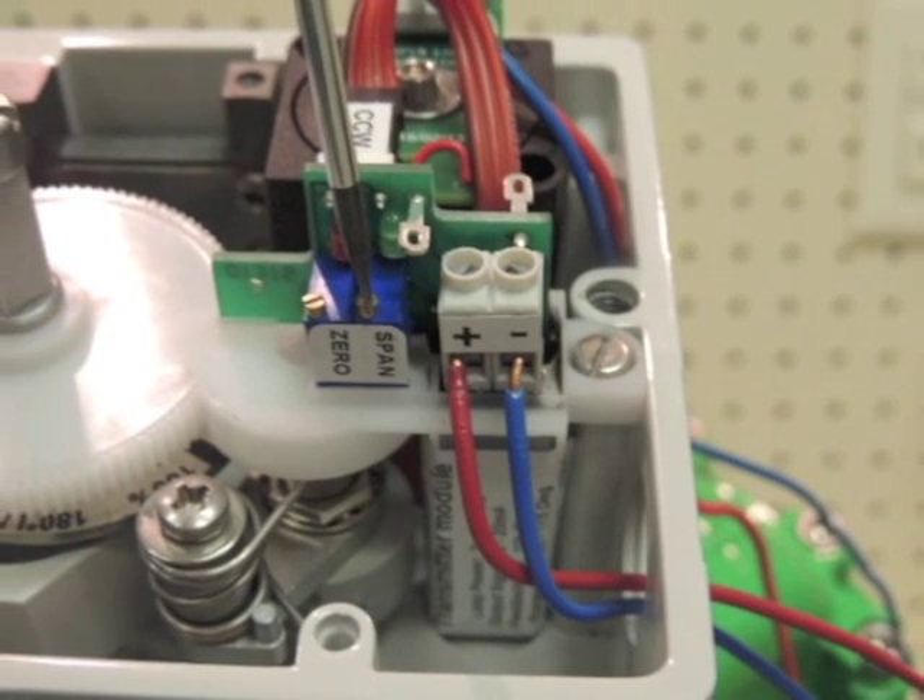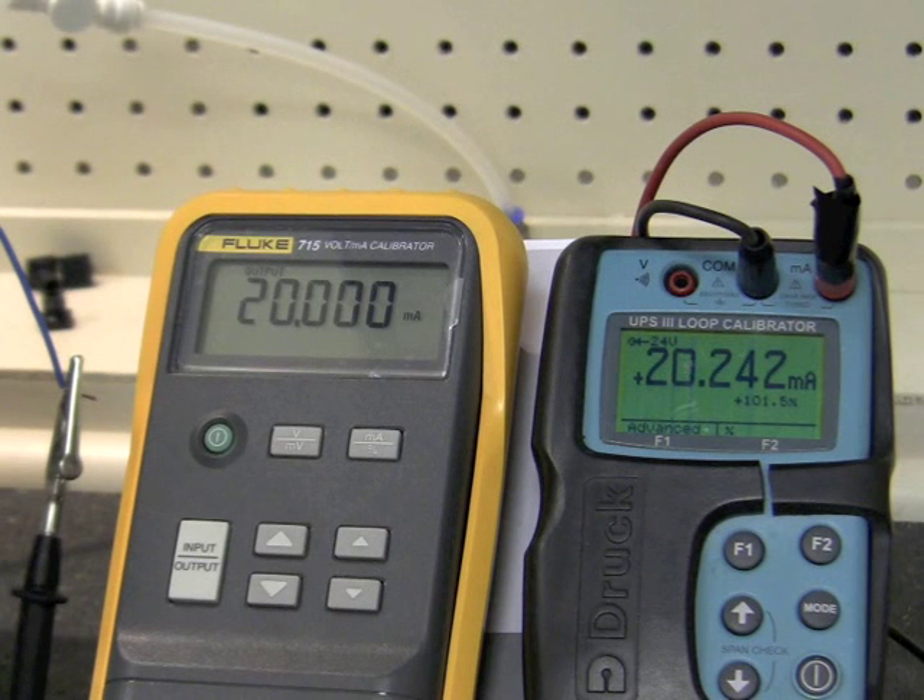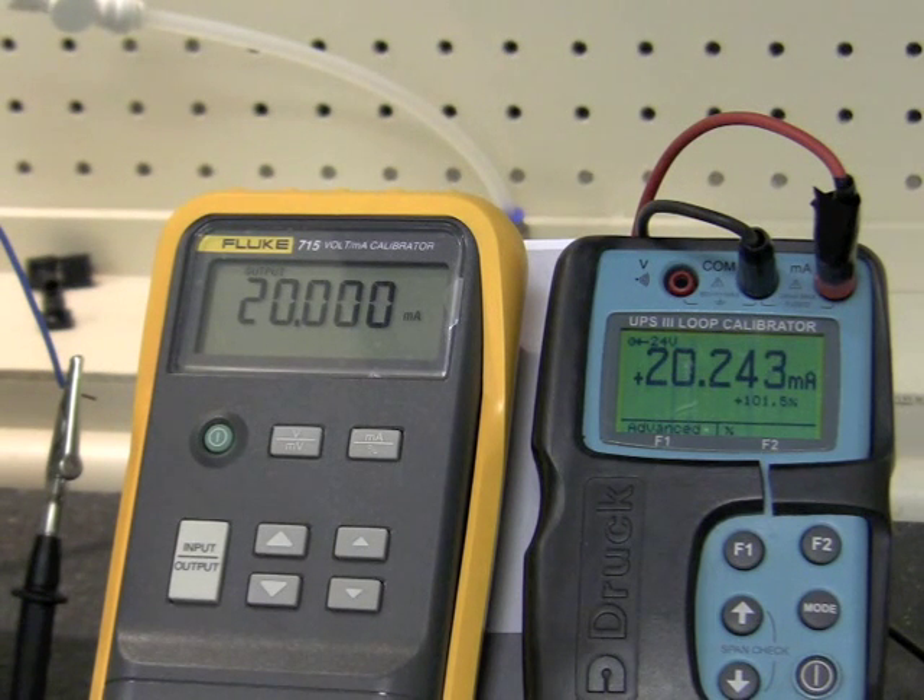Here is where the span trim pot is located. Now we need to input a 20 mA control signal to our I/P and use the span trim pot to trim the 20 mA output on the feedback.